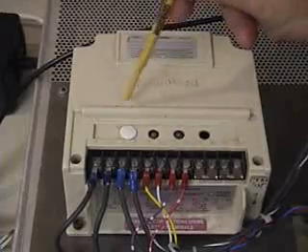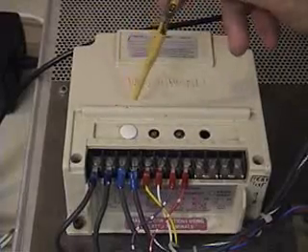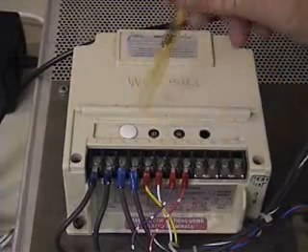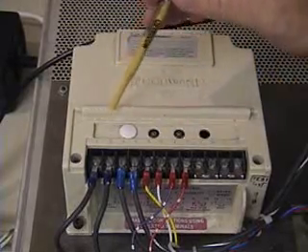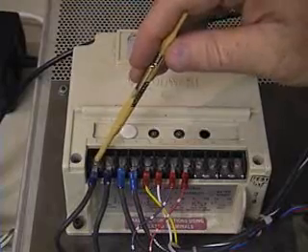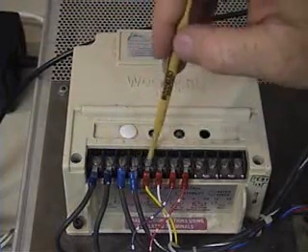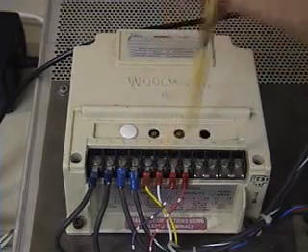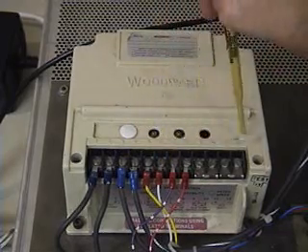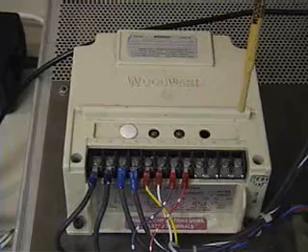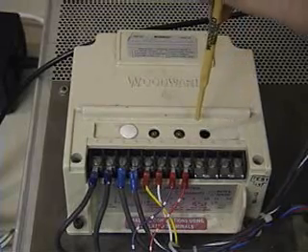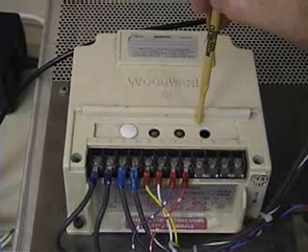This is the electric power governor. It actually controls the speed, sending its output to the actuator. The inputs to the EPG are 24 volt power, and input from the magnetic speed control, with output to the actuator. We have 3 potentiometers on top here to control the PID and adjust the PID parameters to the controller.